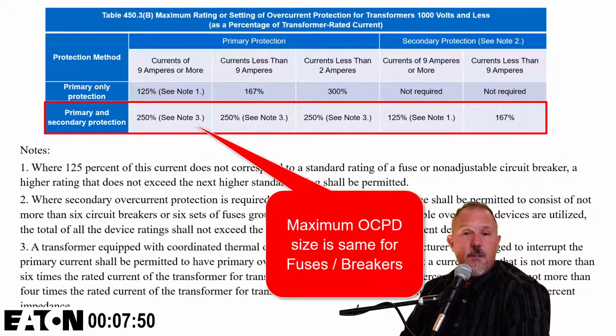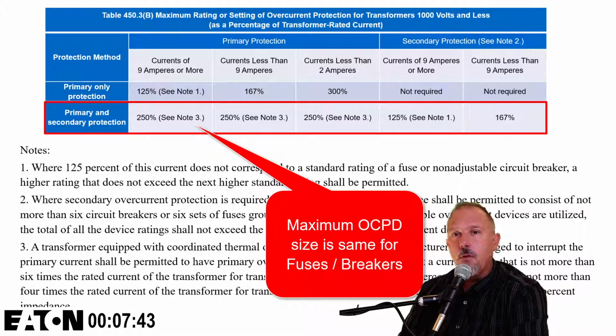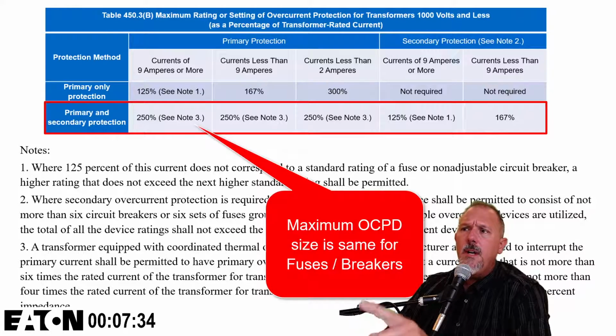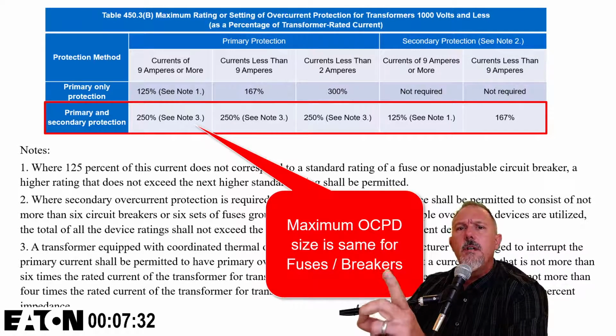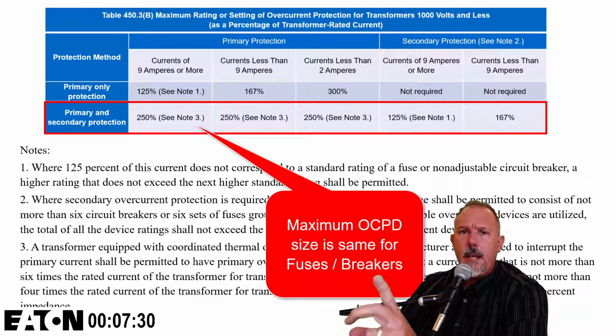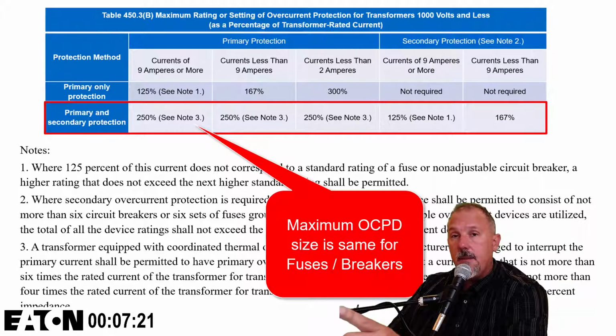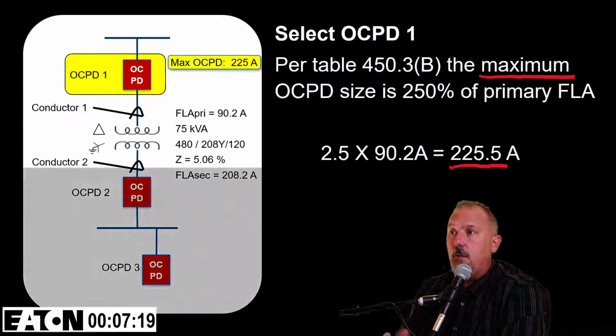I'm not going to go over those, and maybe I will at some point specifically focus on that, but you're back in Article 240 and you're in 408 for the protection of the panel board and the tap rules in Article 240. So secondary transformer, secondary conductor rules in 240. So in any case, I am going to demonstrate the use of 250%. I will also give you an example of 125% on this transformer.